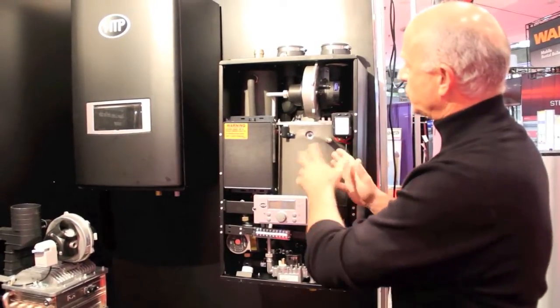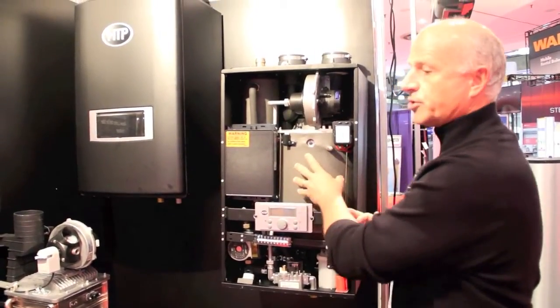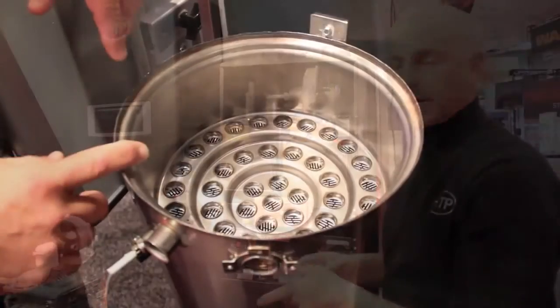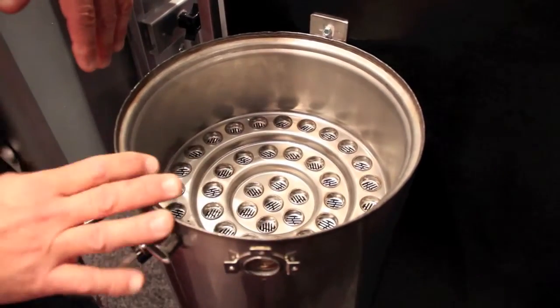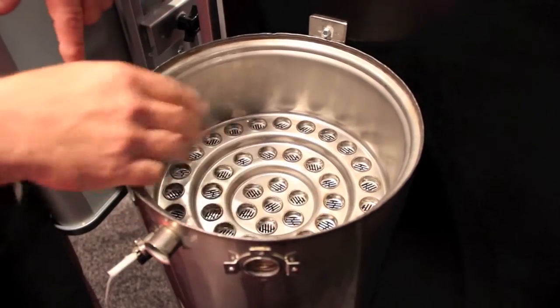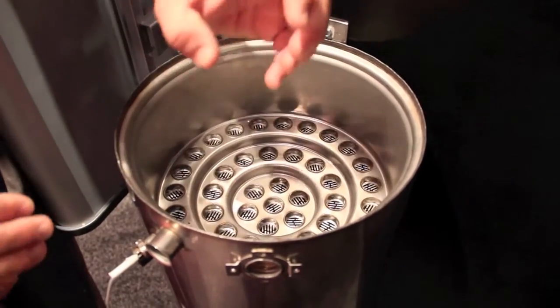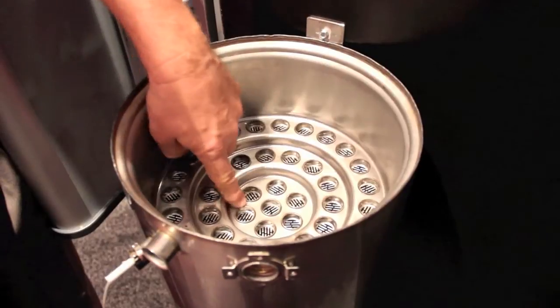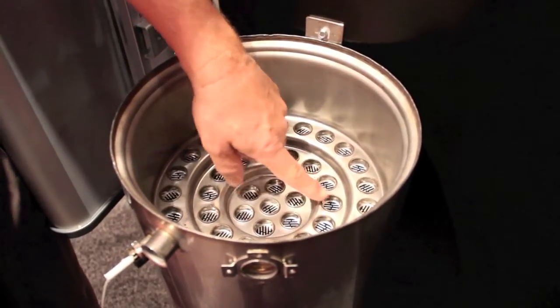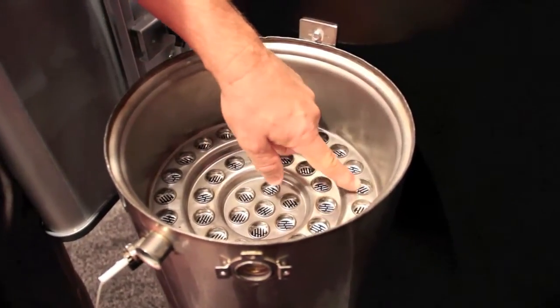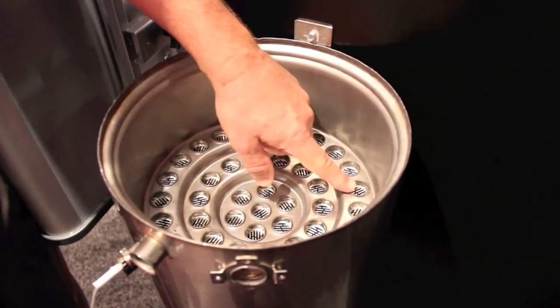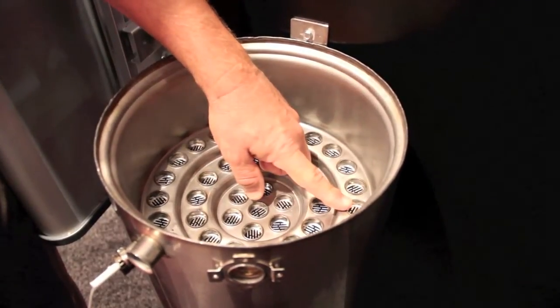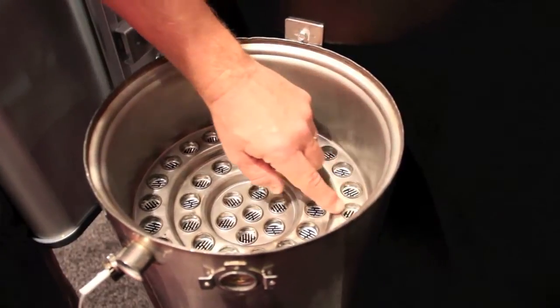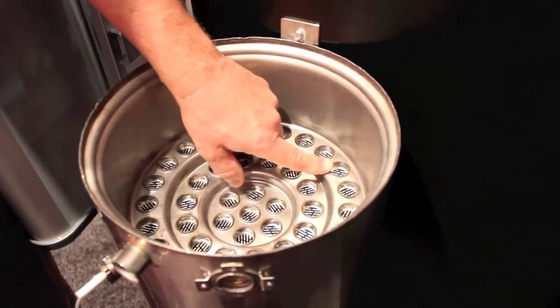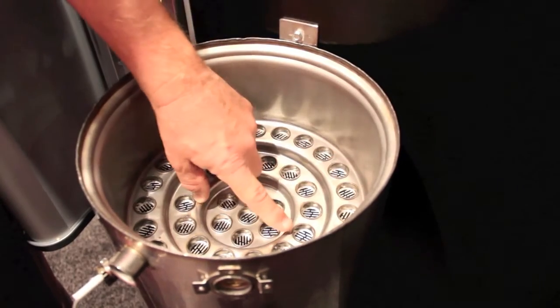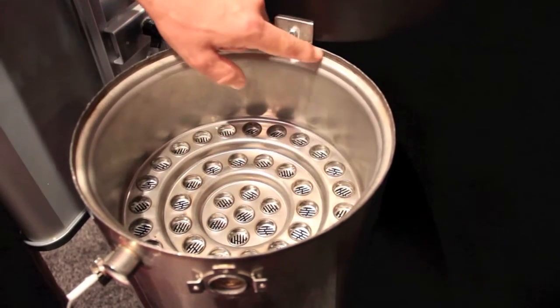So what I'd like to do is show you the heart of the unit, the heat exchanger, and we'll take a look at that. One of the unique features about this heat exchanger, as you can see as you look inside, is the heat exchanger is a fire tube. So you have your fire up here, you're firing down through these tubes. These tubes have aluminum extrusions. You can see these fins inside of here. These fins transfer the energy into the stainless steel tube. Each one of these tubes is laser welded, precision welded, both top and bottom. The top end of this is also welded.